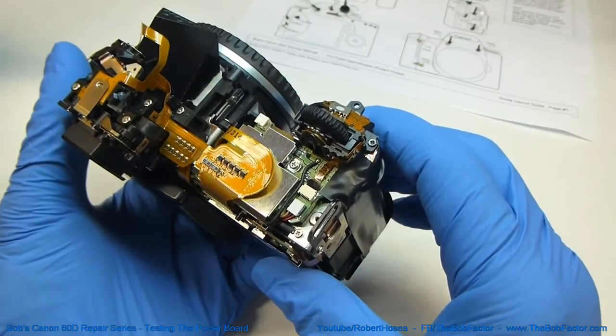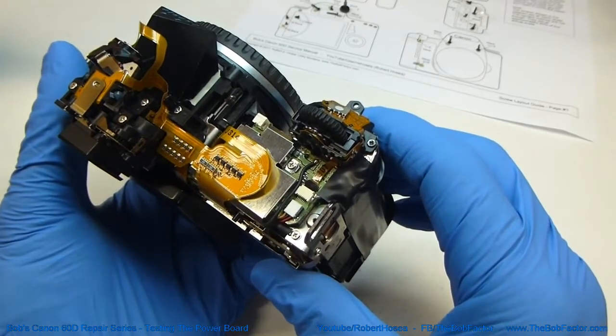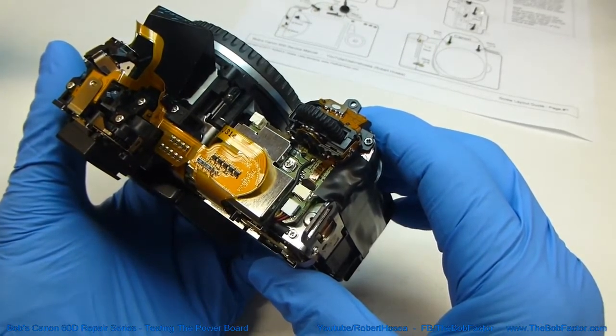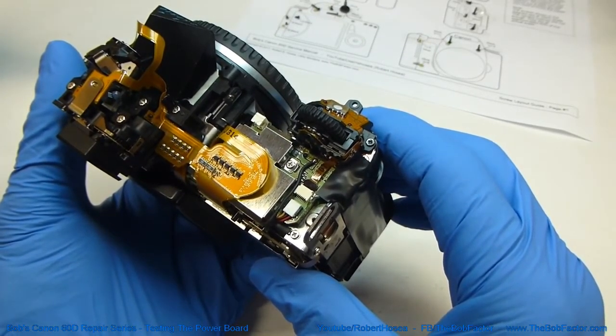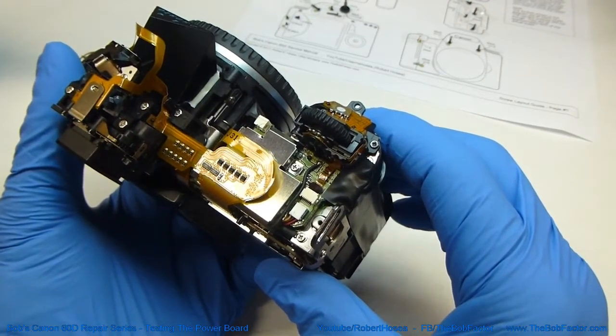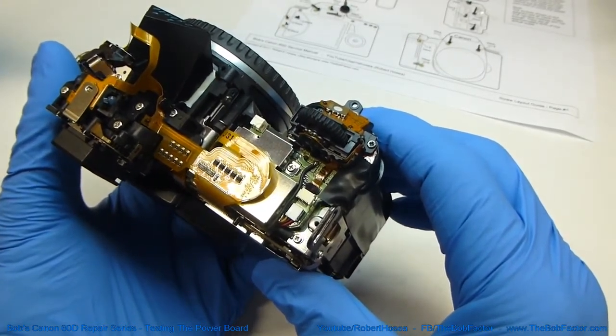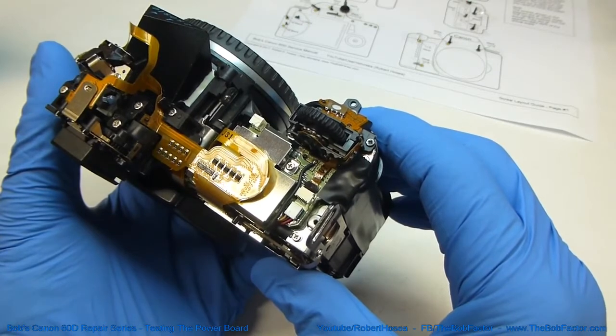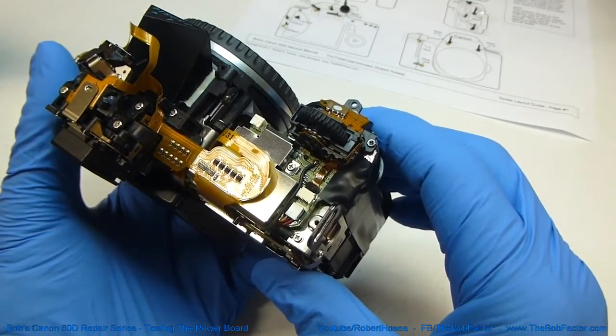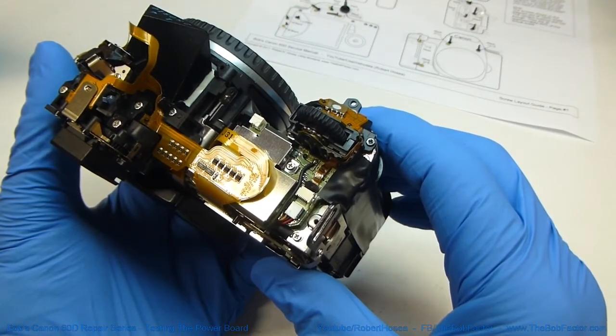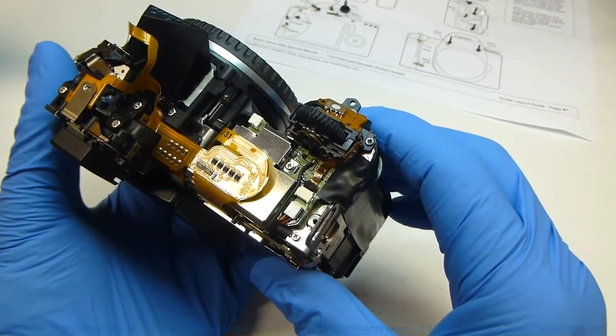So that shows you a couple of places you can test on the power board to get an idea of whether it's good or bad. Now, like I said earlier, you may also get those same readings and the board could still be bad. But if you're not getting those readings, or something real close to it, that probably is a good indication the board is defective.